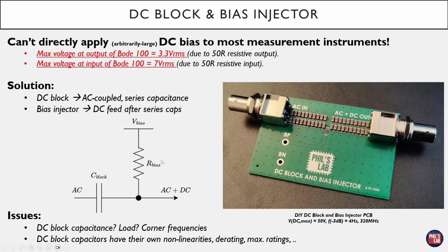The bias resistor is typically around 10 kilo ohms, and the blocking capacitor has to be chosen large enough, given that we're running a 50 ohm based system and measuring low impedances, that the low frequency cutoff is mostly out of the measurement range. That typically means we need a large blocking capacitor due to the high-pass filtering effect, or, as you see here, this is the custom DC block and bias injector I made.